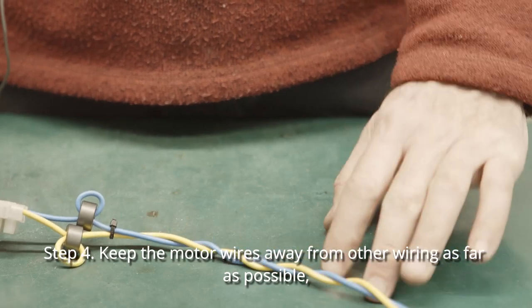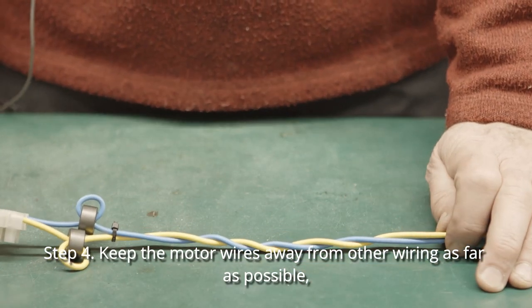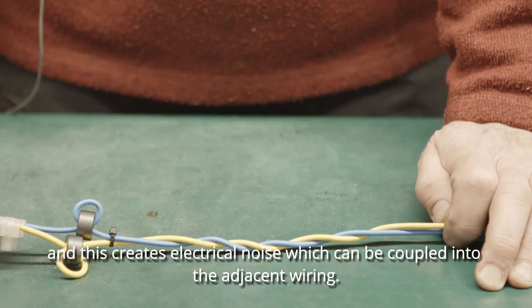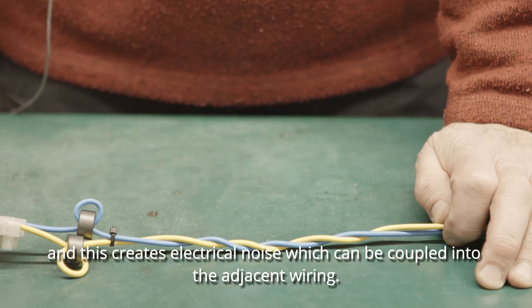Step four, keep the motor wires away from other wiring as far as possible. They are carrying significant currents that are being switched very quickly. This creates electrical noise which can be coupled into the adjacent wiring.